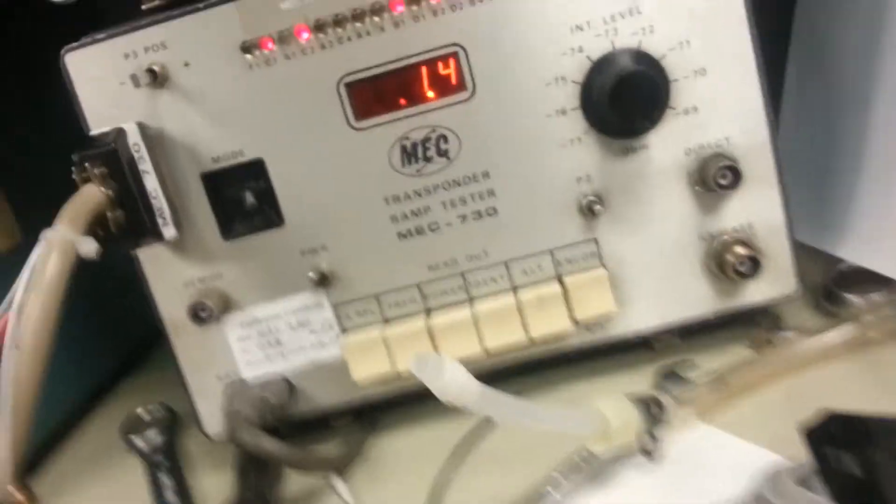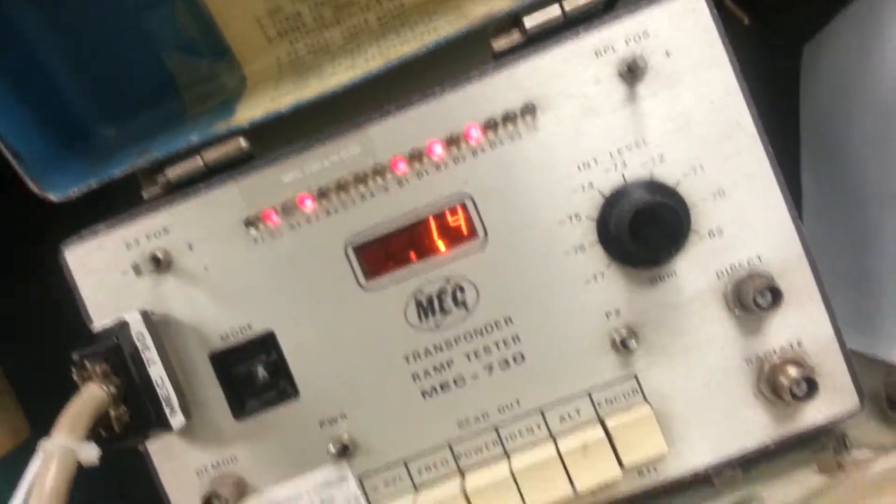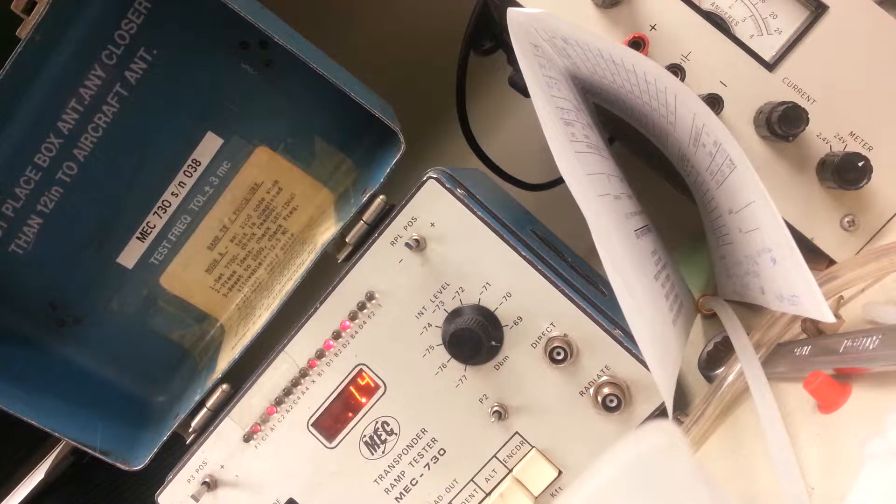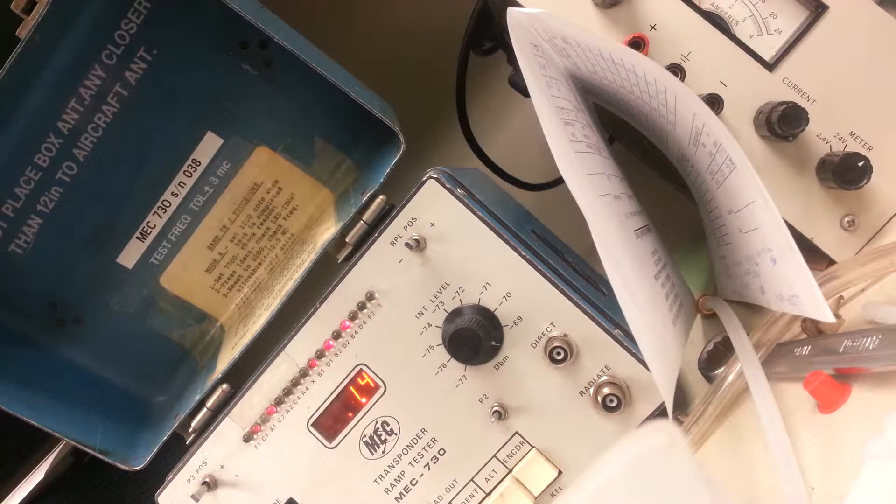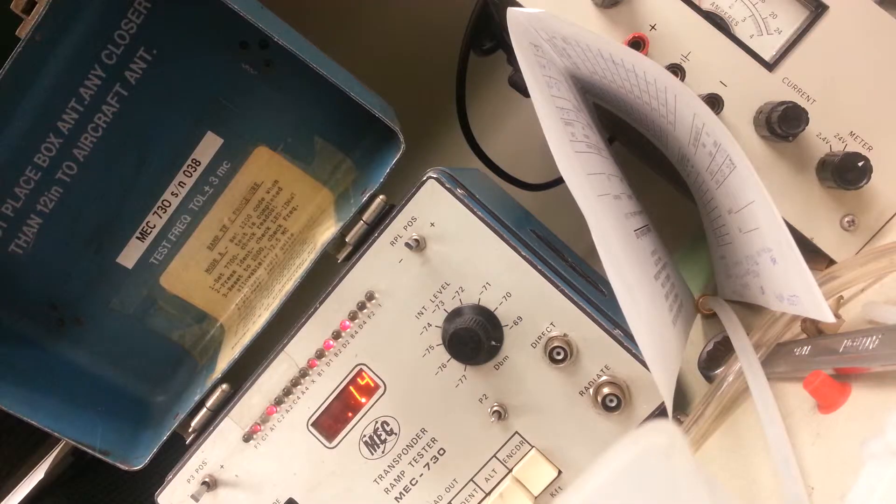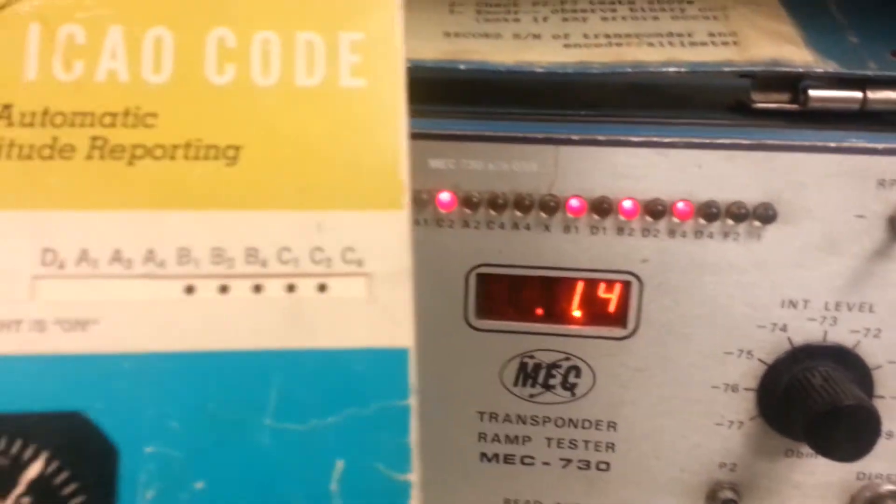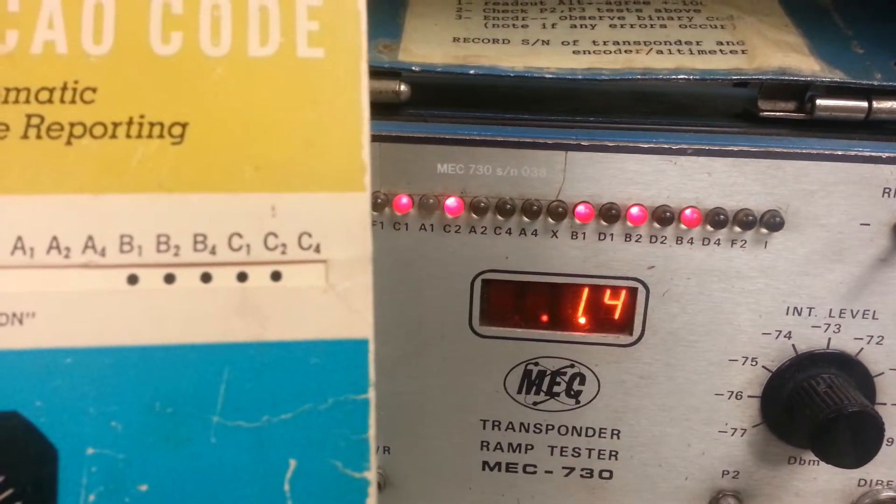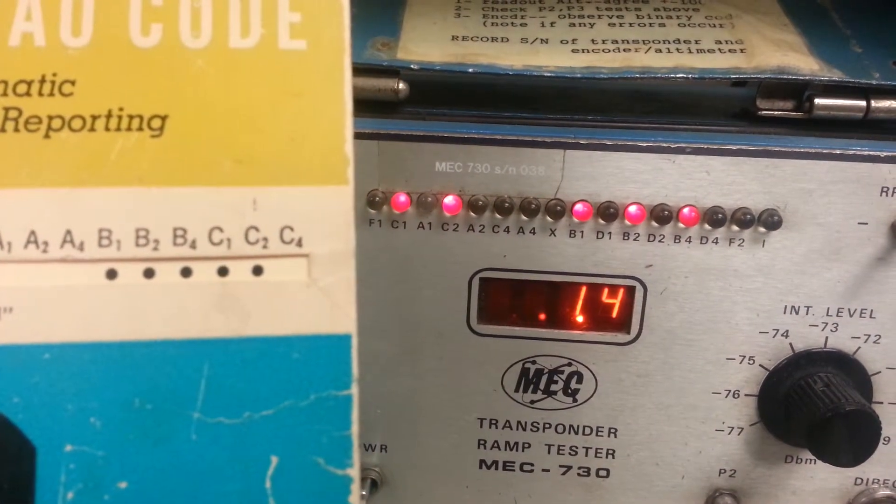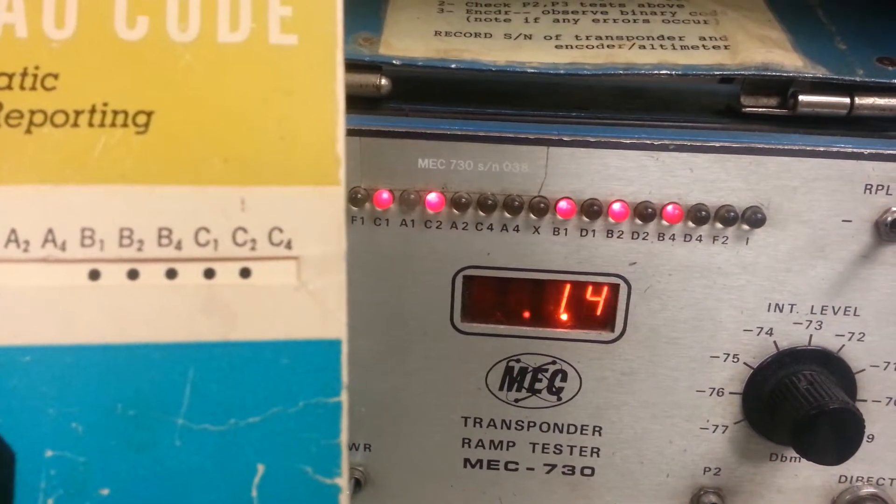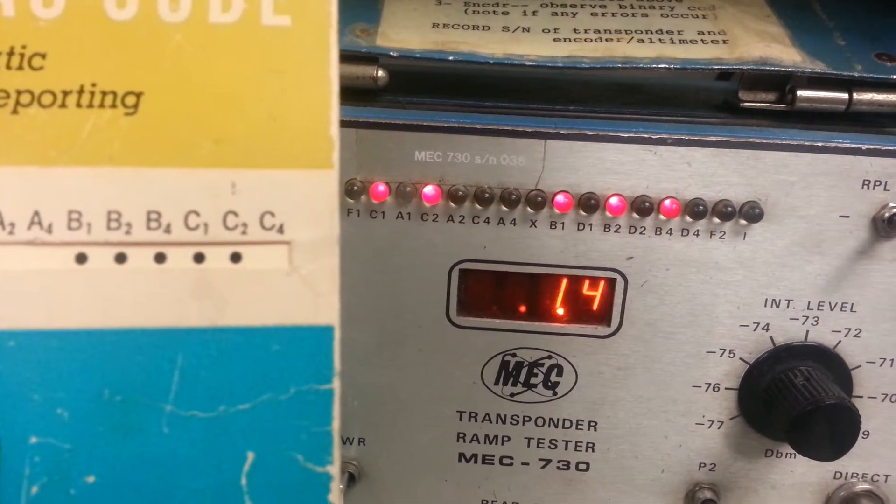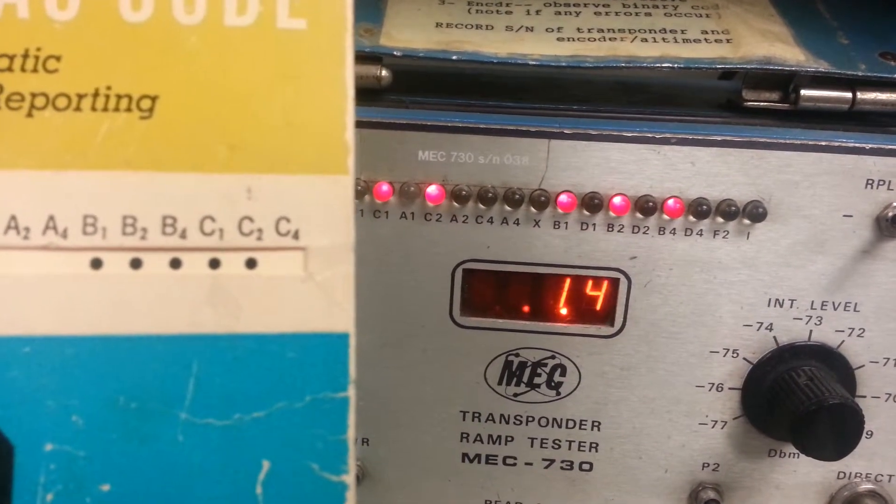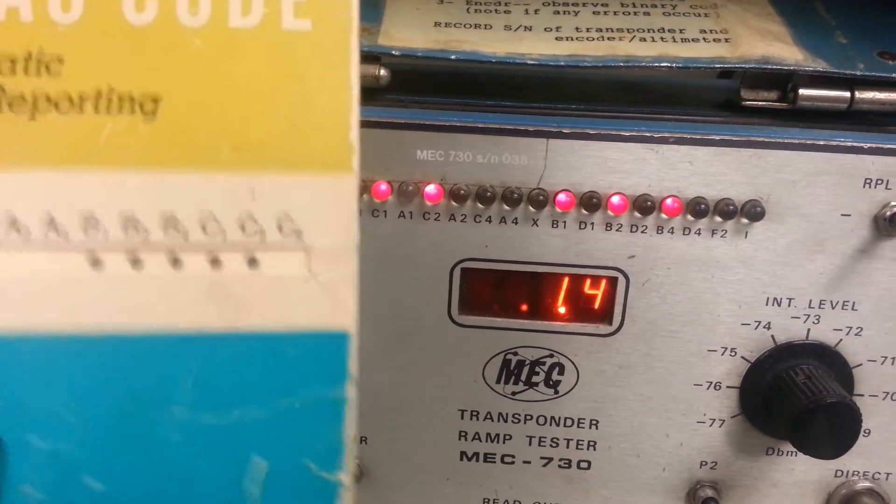So if you take this, kind of hard to do one-handed, let me set you down here for a second. If I take this and I put it on 1,400, is what the encoder is reading. That's exactly what I got: C1, C2, B1, B2, and B4. So the difference between 4,100 and 1,400 is the A4 bit.